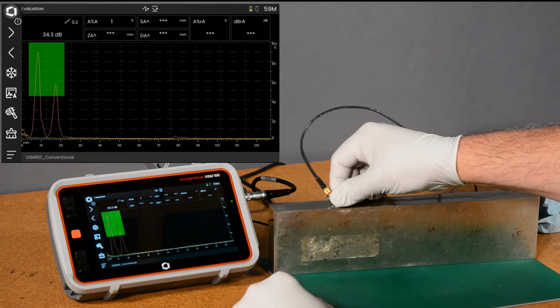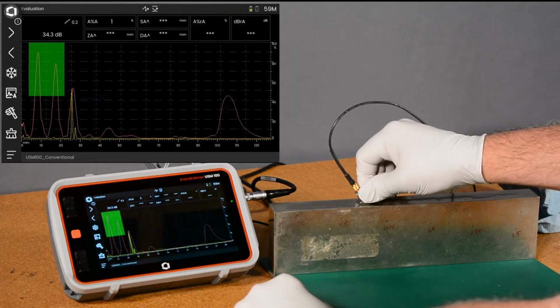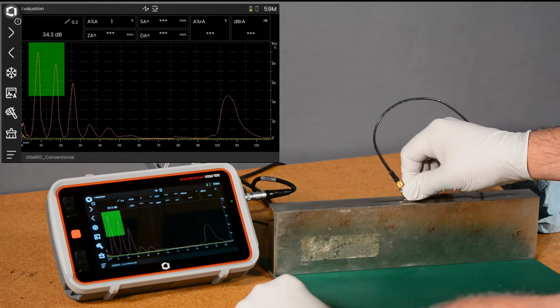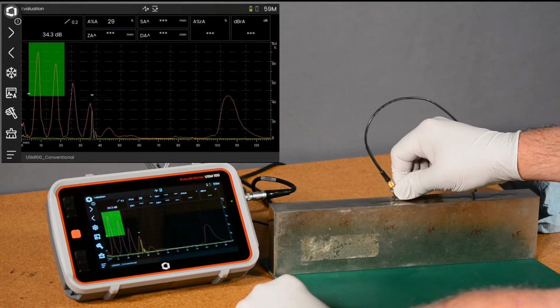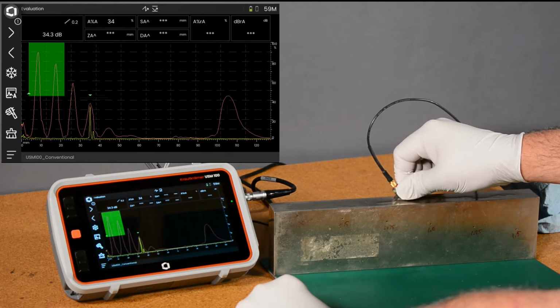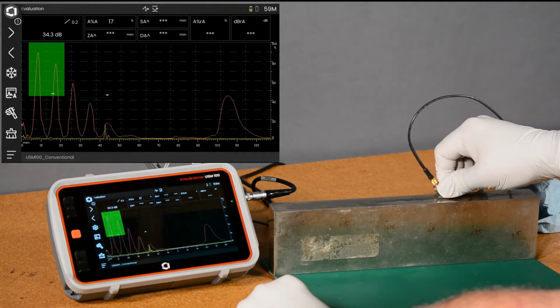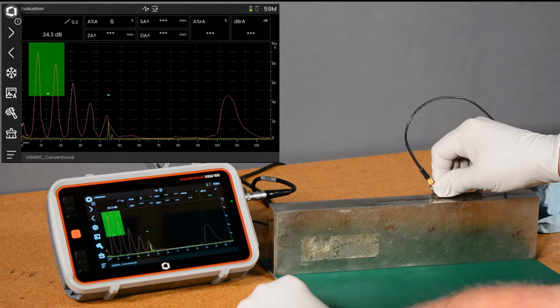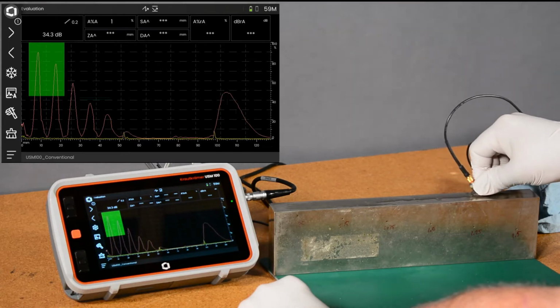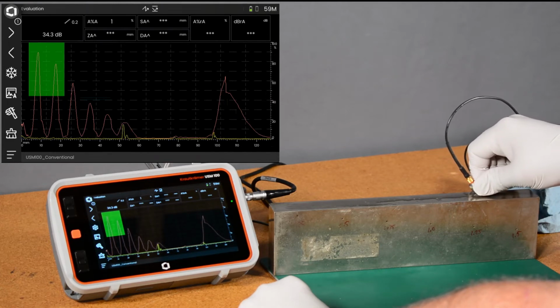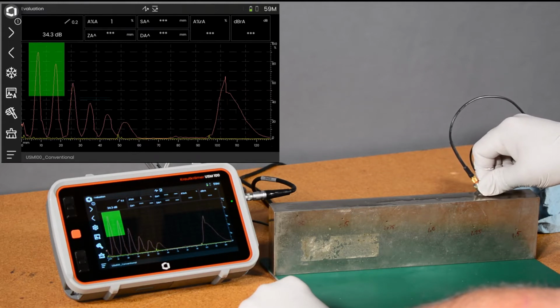And then I can run right across my series of holes. And as I peak up on each one of these holes, you see the envelope just keeps showing me the peak amplitude I get at each spot. So it helps me get accurately peaked up on each one of these. In some of our previous instruments we would have had to find each one of these holes, peak up, reach back to the instrument, hit the calibrate button. But here I'm able to simply focus on moving my probe and getting each one of my peaks recorded.